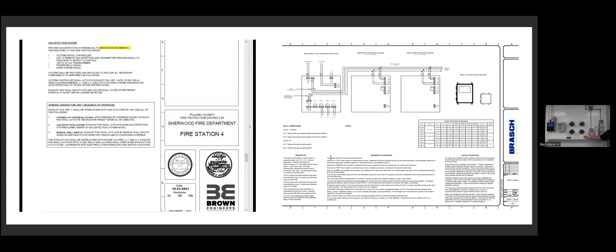One thing Brasch does differently than some other manufacturers is that everything we put together for a project is pre-programmed, pre-addressed, and pre-wired before it goes out the door. In the specification you can see we have low alert, high alert, and alarm set points configured, so when the product gets built into the specification, all those parameters are pre-built into the system and ready to go in the field when it ships to the customer.